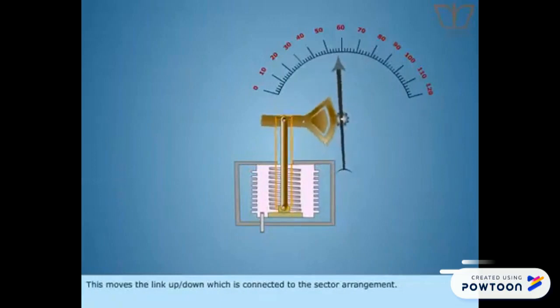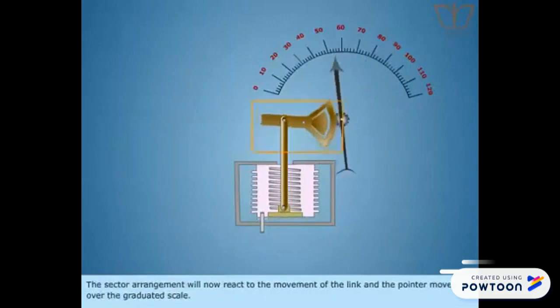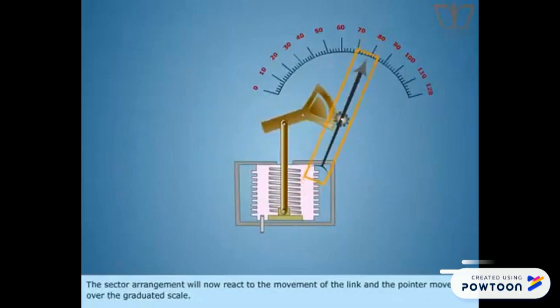This moves the link up or down which is connected to the sector arrangement. The sector arrangement will now react to the movement of the link and the pointer moves over the graduated scale. The readings on the graduated scale indicates the pressure value.